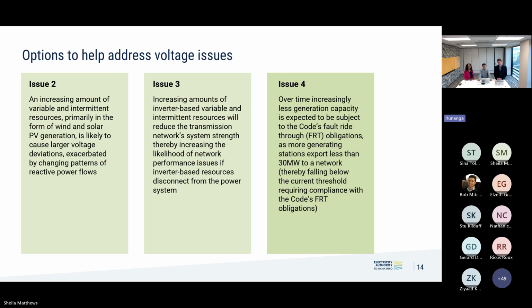The second of the voltage issues, which we call issue 3 out of the 7, is that the reduction in system strength is also likely to cause performance issues from inverter-based resources, increasing the likelihood of them disconnecting from the power system. And we've seen this overseas, where the settings in the IBR are such that if there's a reduction in the power system quality, the inverters trip, and to protect themselves, the protection mechanisms kick in, and we get disconnection from the power system. So what we're looking at here is ways in which we can deal with this issue.